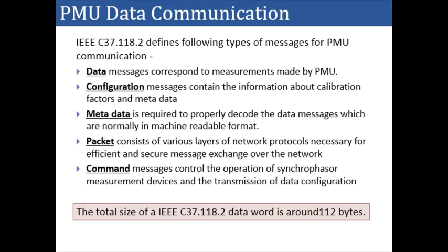In this video, we will discuss the phasor measurement unit data communication. PMU data communication related information and the standard required for PMU data communication is defined in IEEE C37.118.2, which defines the following types of messages for PMU communication. First one is data messages, which corresponds to the measurements made by PMU. Second is configuration messages, which contain the information about calibration factors and the metadata.